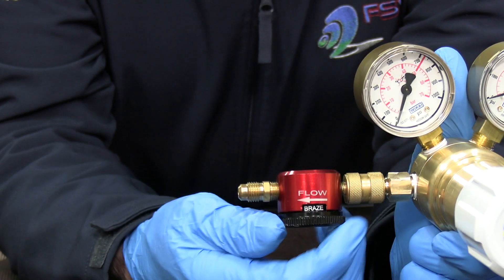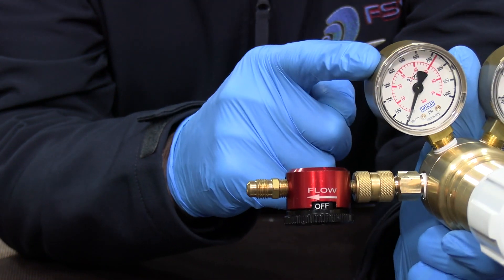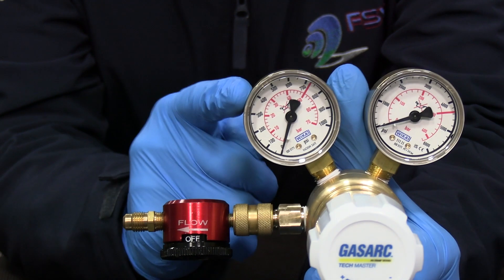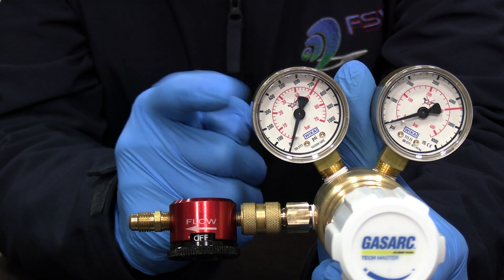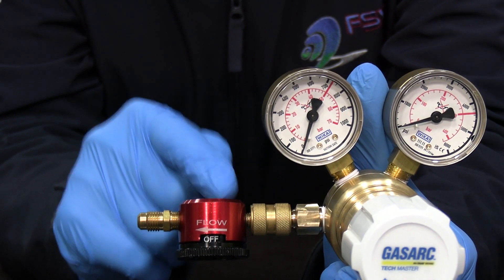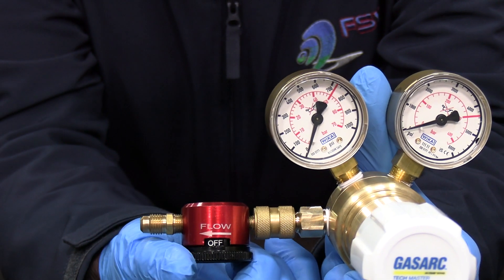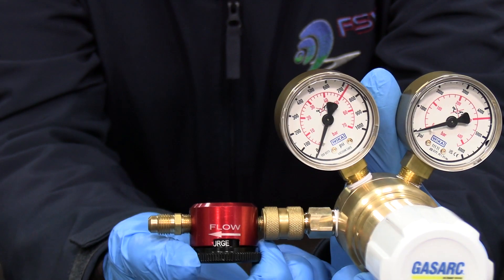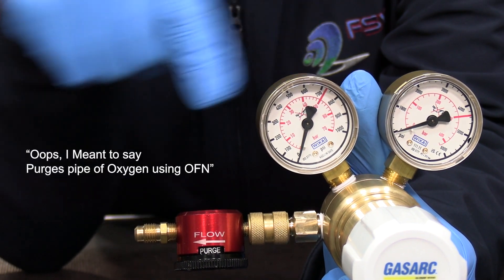So what you do, you start in the OFF position. You make sure you put 5.0 PSI into the regulator, coming out of the regulator into this purge and braze tool. Then you turn it one click to purge. What purging is doing is it's purging the pipe of oxygen so you just have pure OFN there.